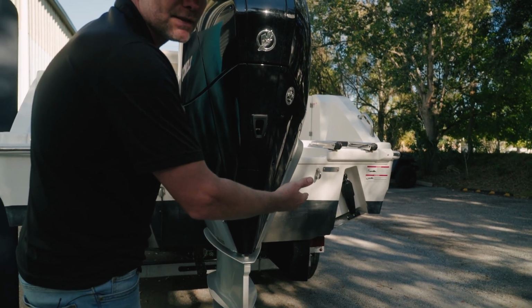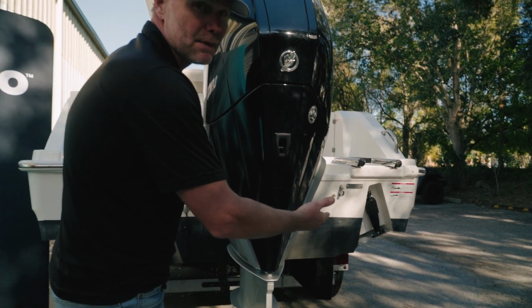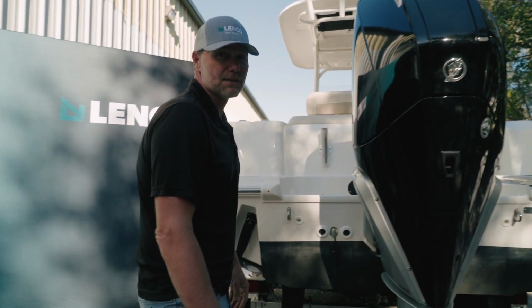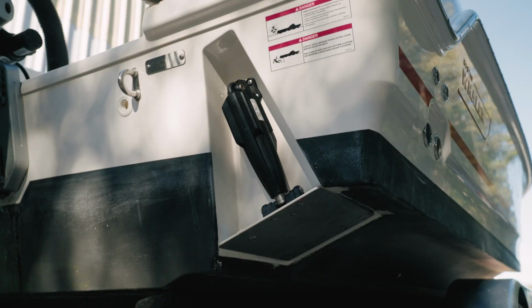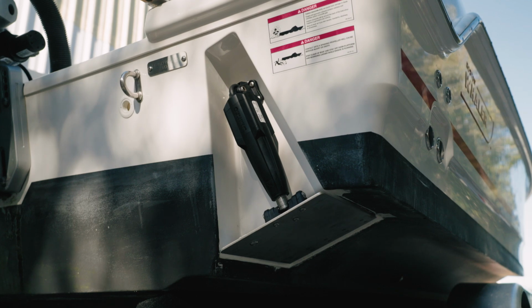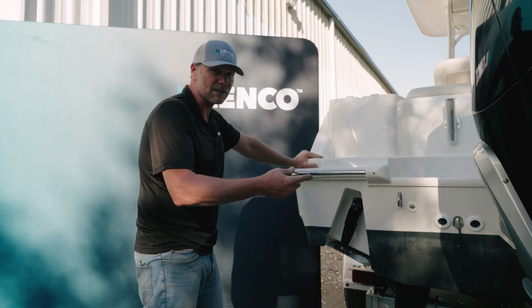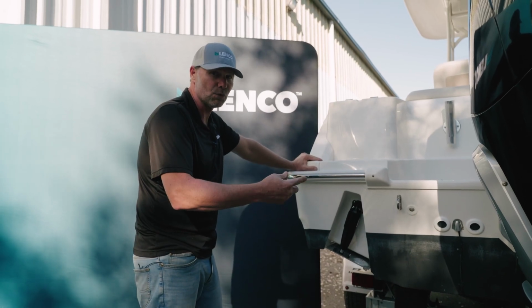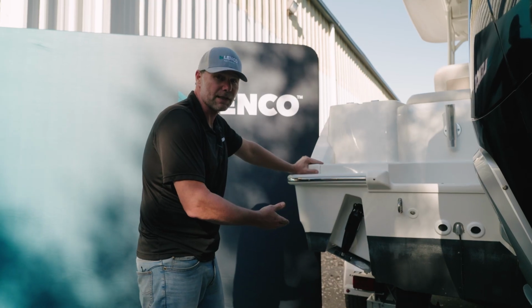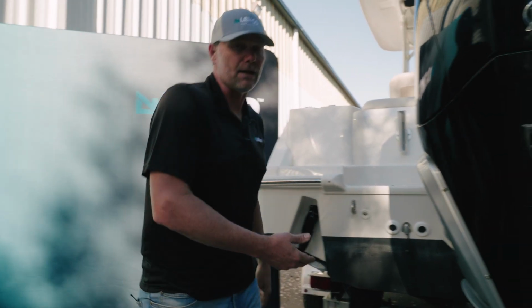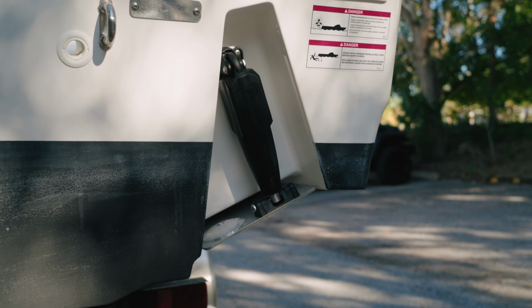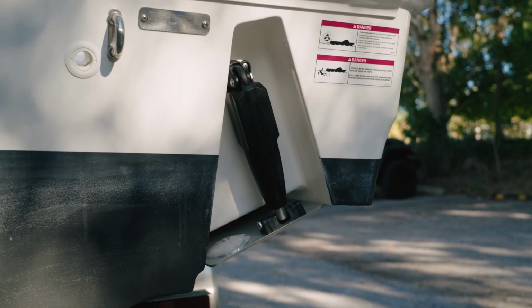So we're going to press the up button on the keypad and switch sides to make it go to the starboard side. Now that Ryan has pushed the up button on the keypad to flip which side the actuator is commanded to move, you can see that the port actuator has stopped oscillating, and now the starboard actuator, which is the correct side, is oscillating.